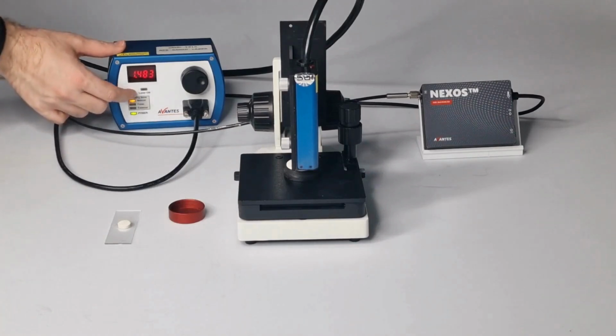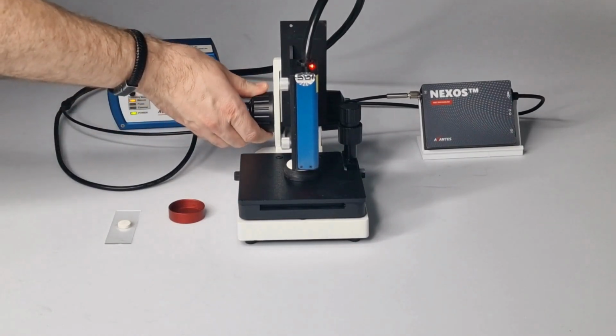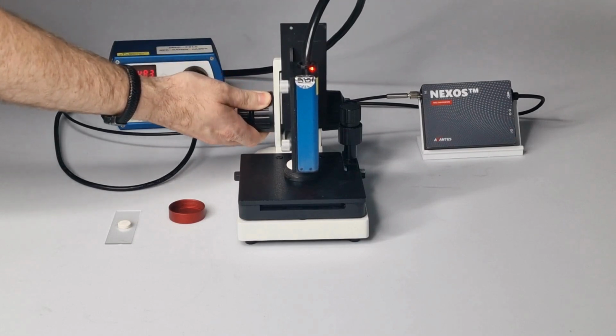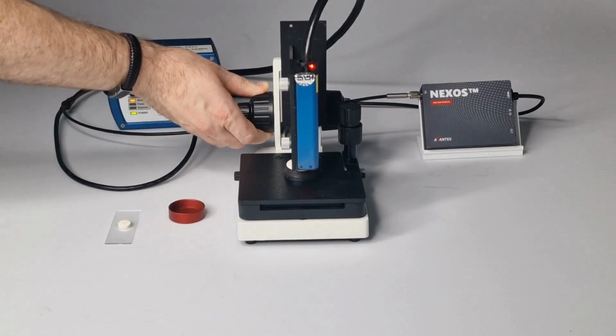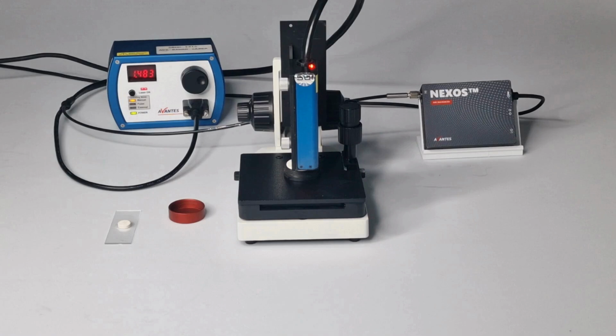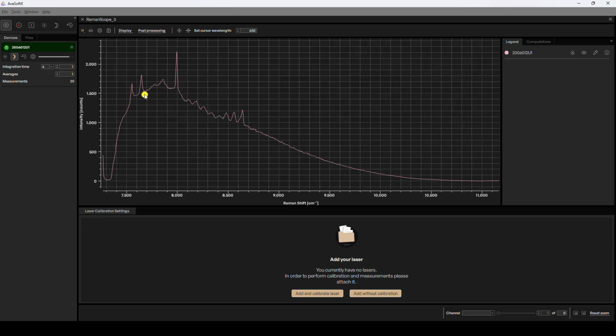Turn on the laser. Align the laser by moving the probe a few millimeters up and down. The highest reflection intensity from the reference material indicates correct alignment, after which you can add the laser in the software. You can add the laser with or without calibration.